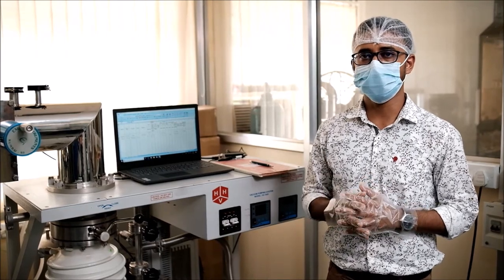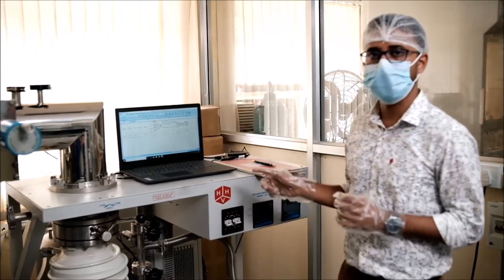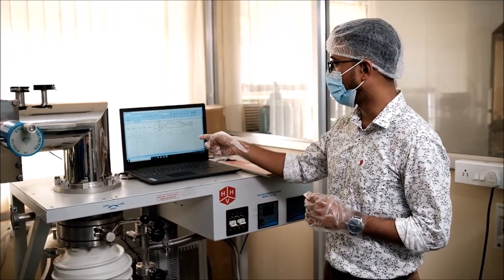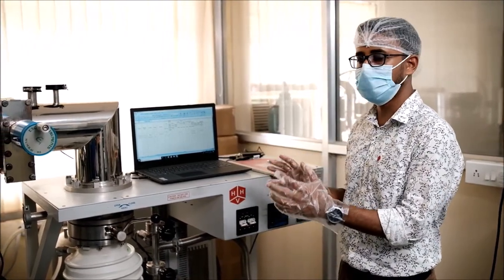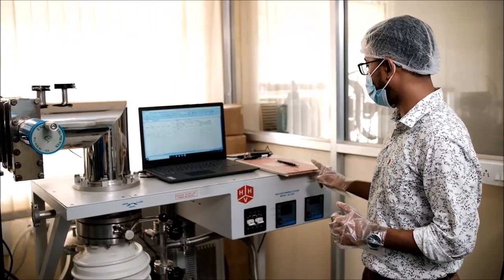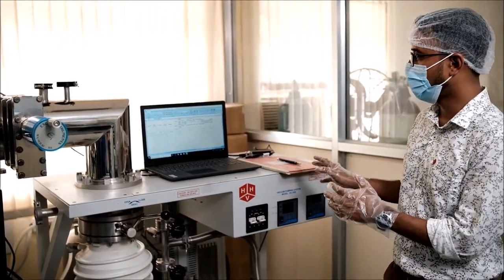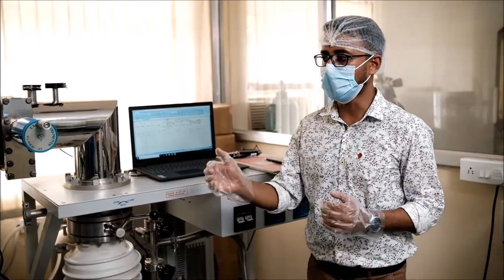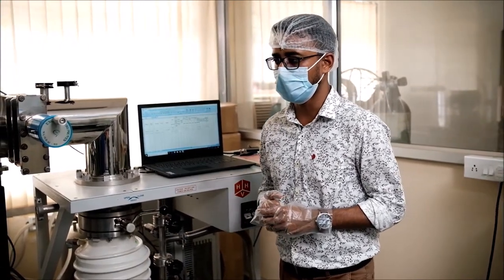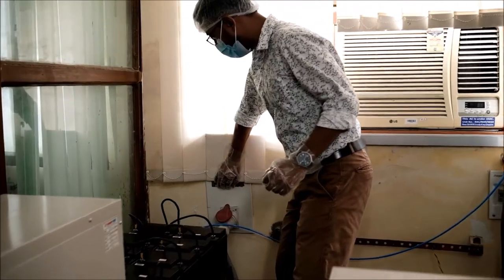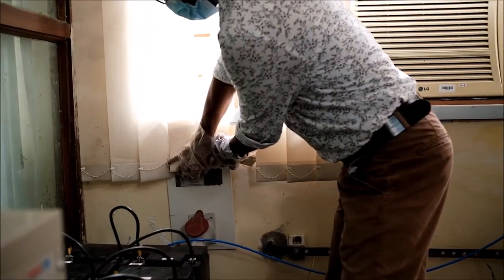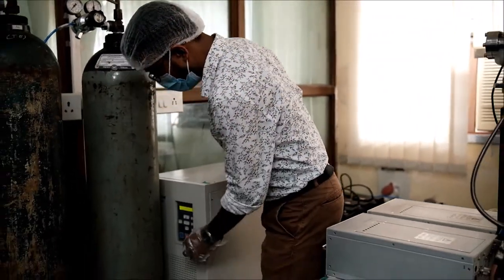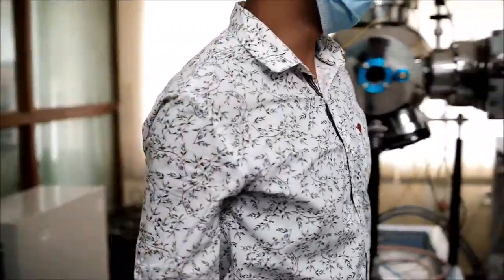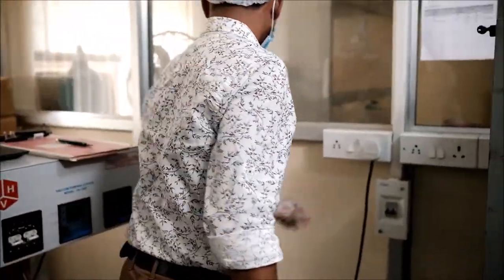So before we start the deposition, we first have to make an entry in the logbook. We have a soft copy of the logbook, so we'll enter all the detailed deposition parameters onto it, and then also on the hard copy. After making the entry in this logbook, we'll start the deposition. First we'll power up the system, and then we'll do the process one by one. First we'll power up the MCB of the UPS, and then switch on the UPS, and one by one I will switch on all the switches.